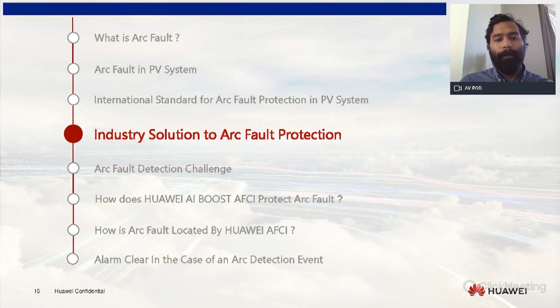You have two cases. First, when the inverter itself doesn't have built-in arc fault circuit interruption capabilities, then you could have a DC combiner box with AFCI capabilities, or just a box that has AFCI capabilities. The problem with this is that it brings higher costs to your installation, and the high frequency switching of the inverter and the other components could interfere with the reading of this box. So the reliability of AFCI detection of this type of solution is normally not very accurate.